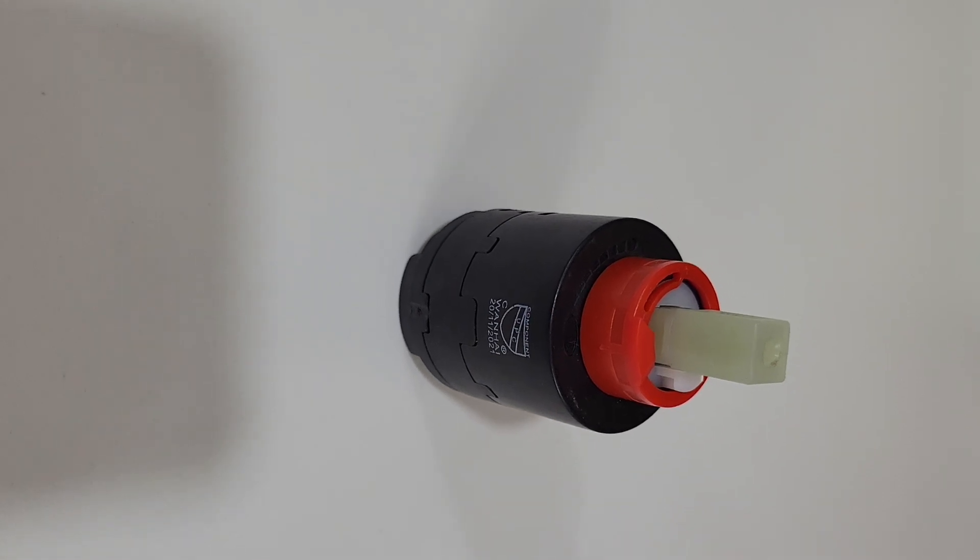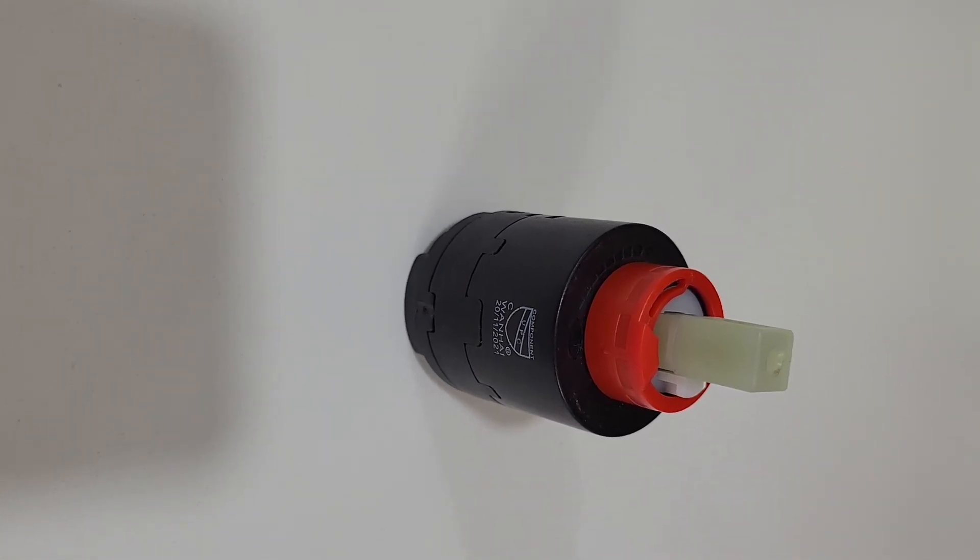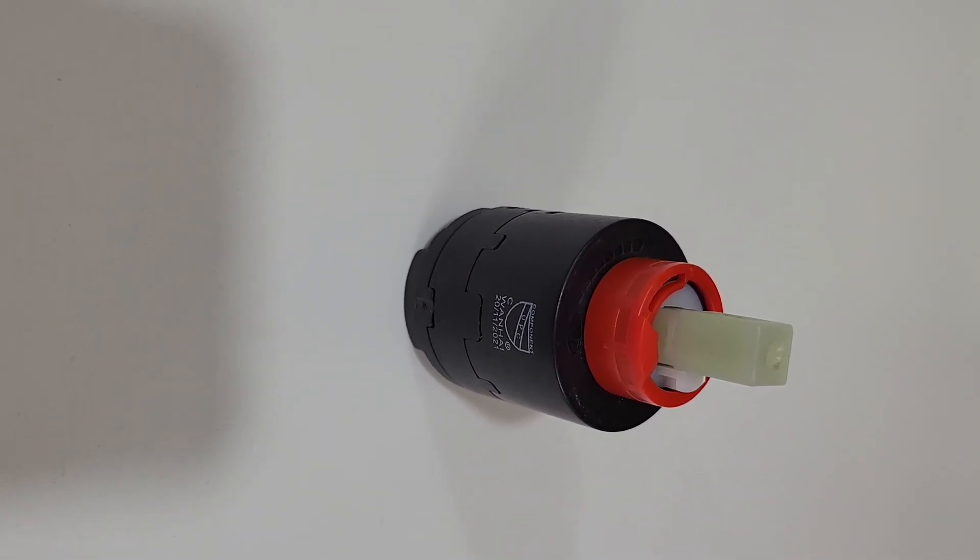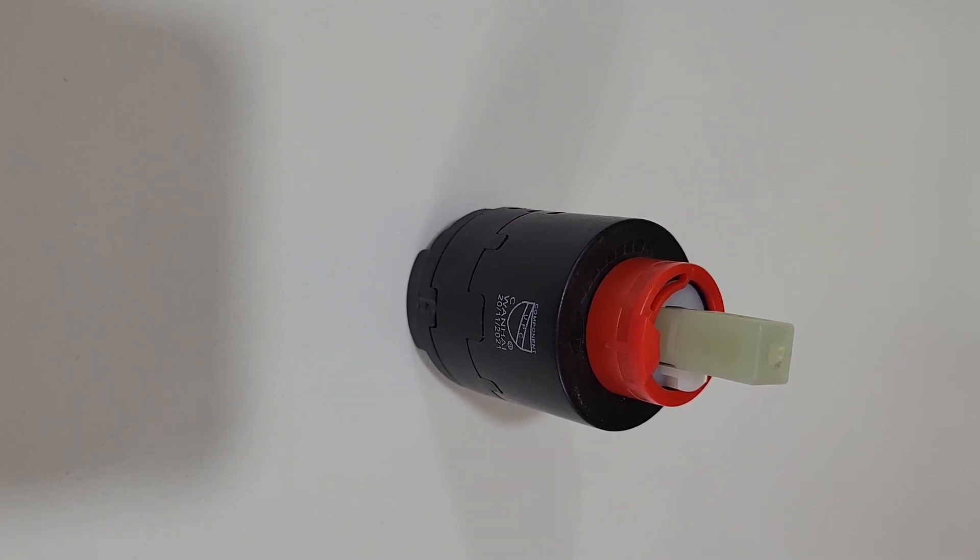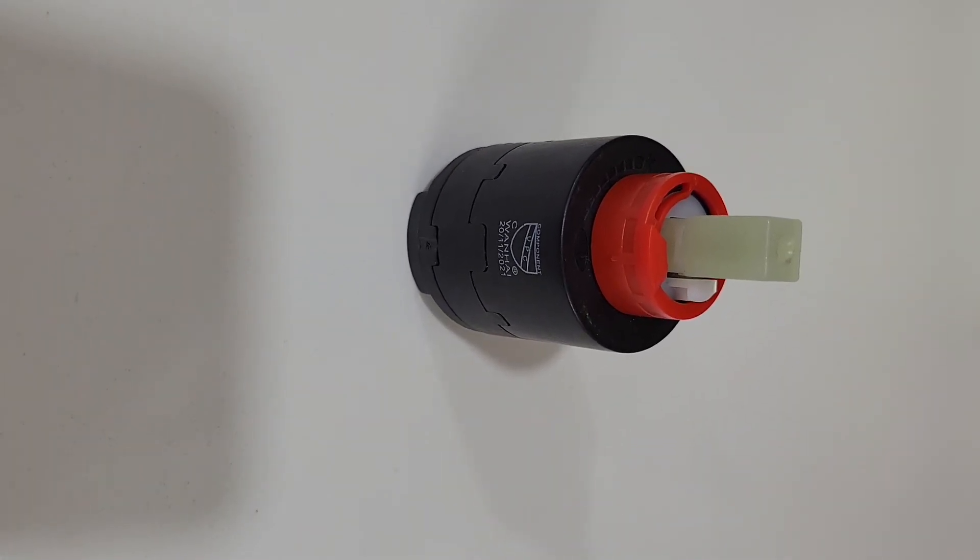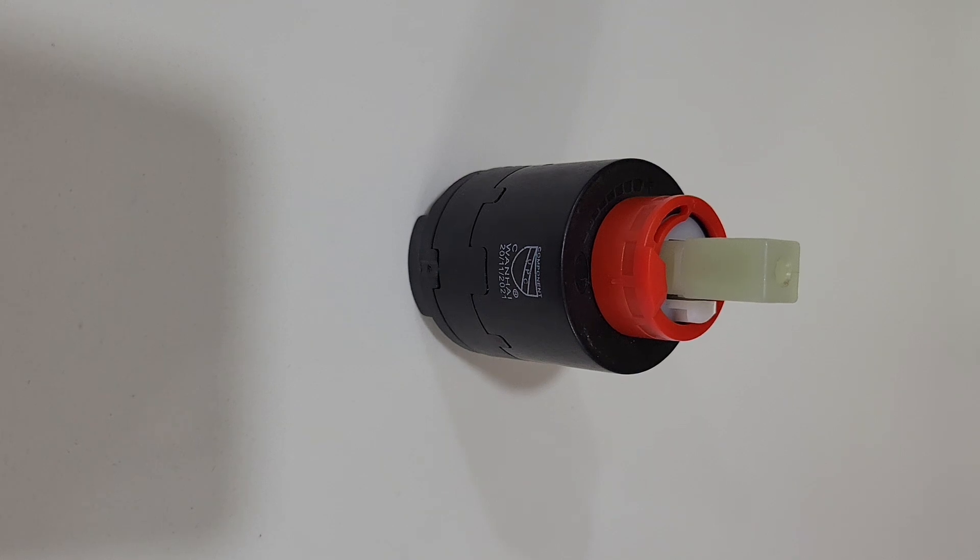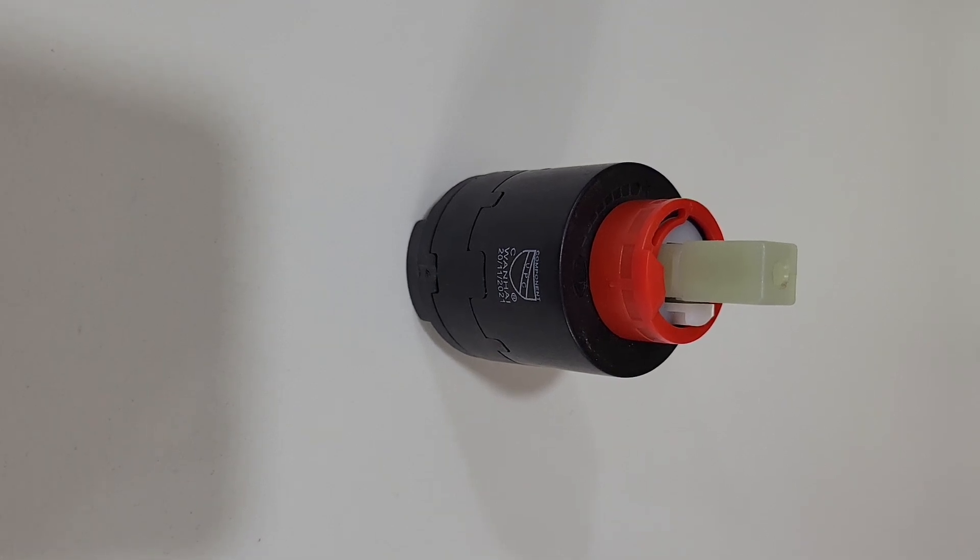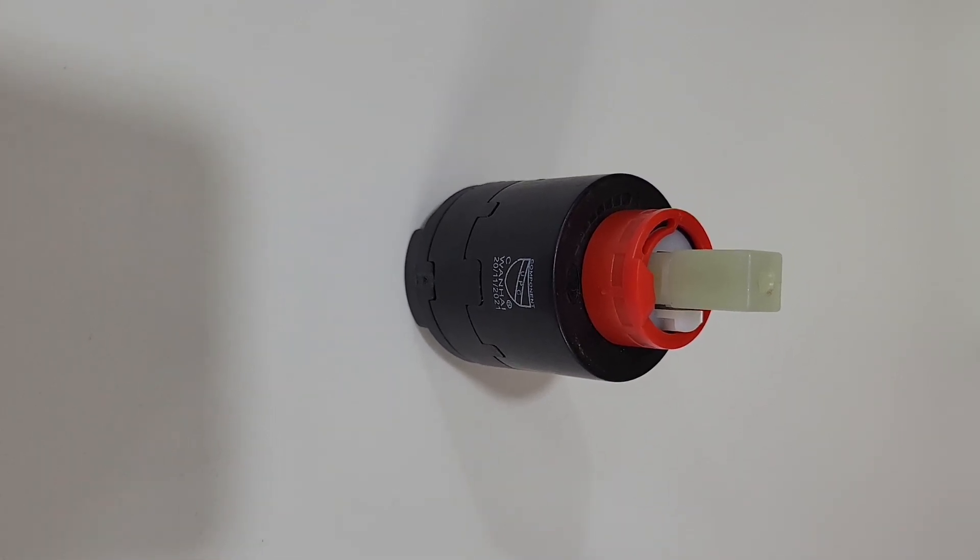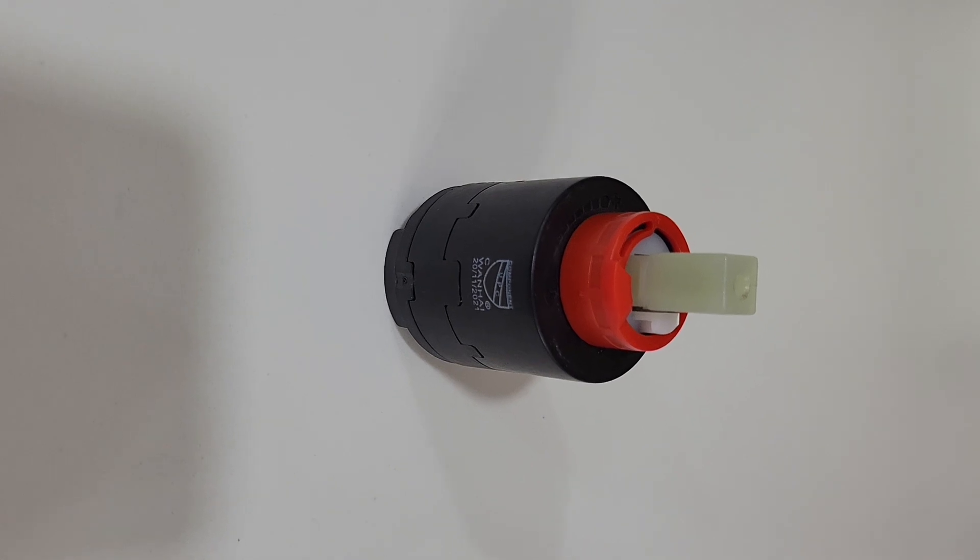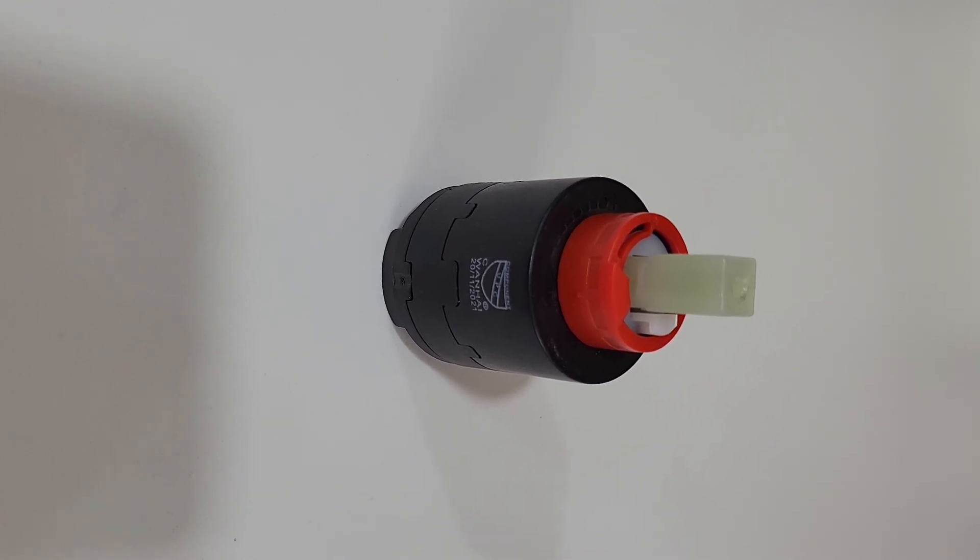Pressure balancing valves duty is to maintain constant temperature of the water coming out of your shower or faucet and prevent scalding. With older style mixers, water temperature would spike up from shower or faucet every time when cold water was opened at the same time anywhere else in the house because of sudden cold water pressure drop.